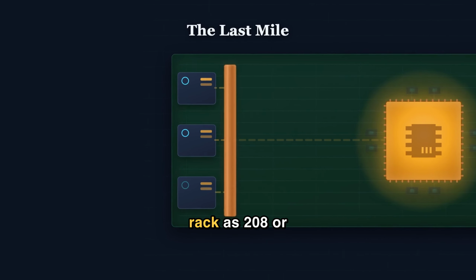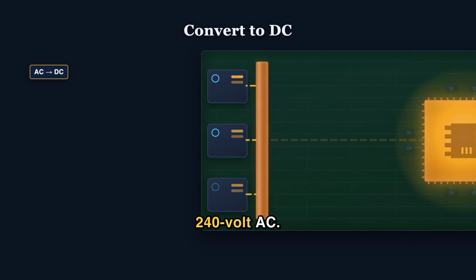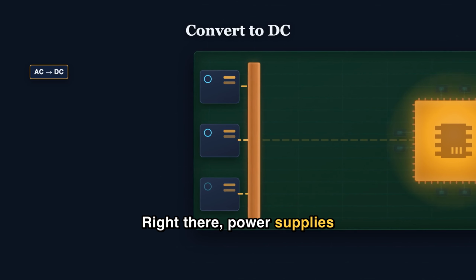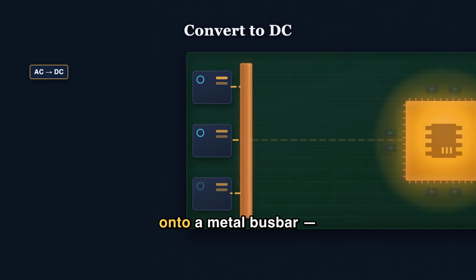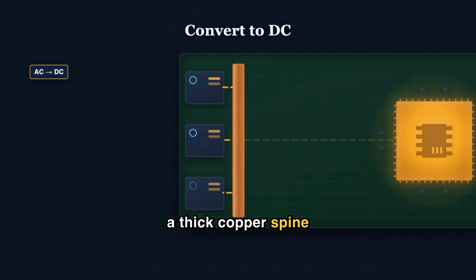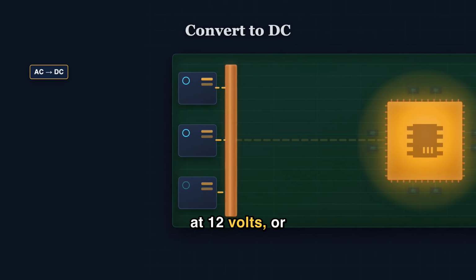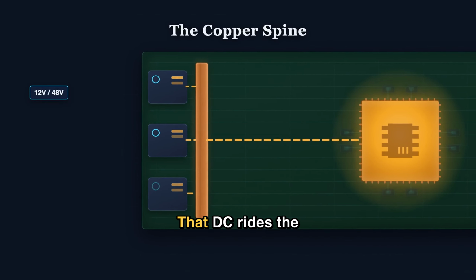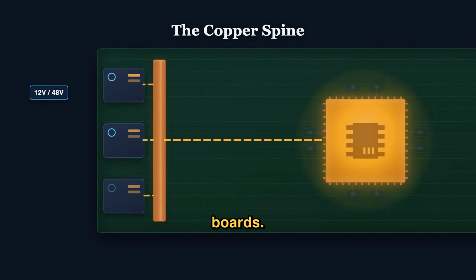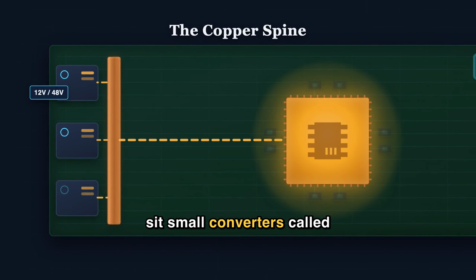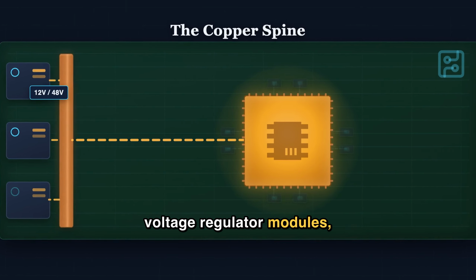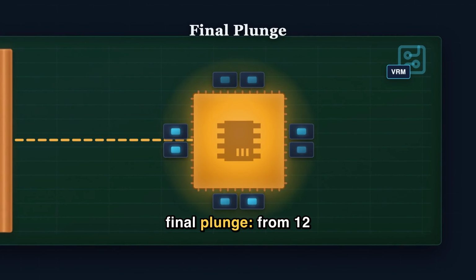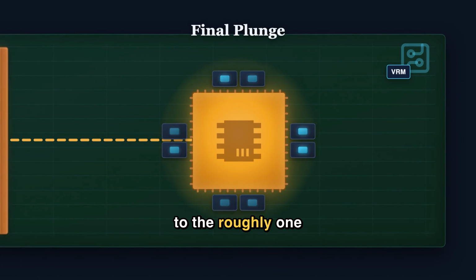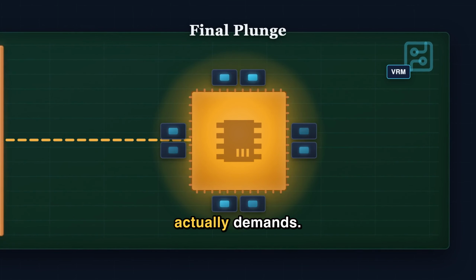Power arrives at the rack as 208 or 240 volt alternating current. Right there, power supplies convert it to direct current and drop it onto a metal busbar, a thick copper spine running up the rack, at 12 volts or in newer designs 48. That direct current rides the busbar straight to the boards. And on each board sit small converters called voltage regulator modules, sitting inches from the silicon. Their job is the final plunge. From 12 or 48 volts down to the roughly 1 volt the GPU core actually demands.